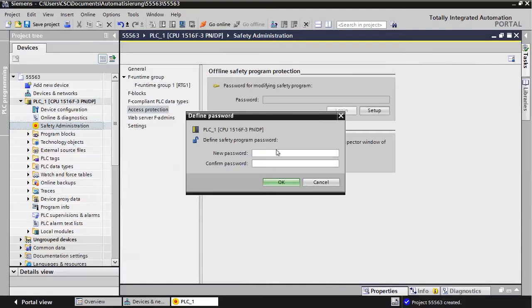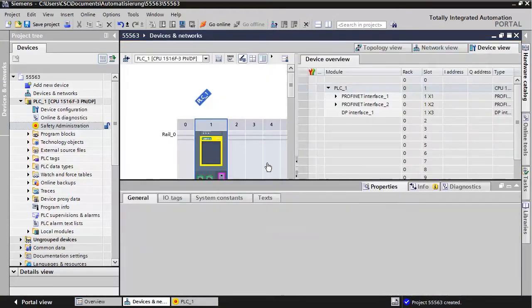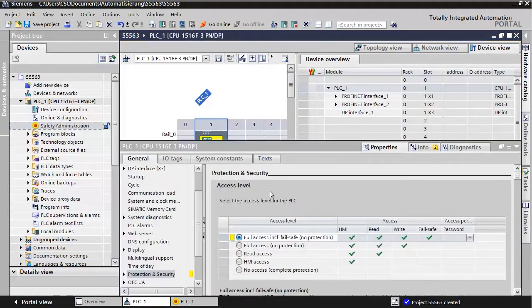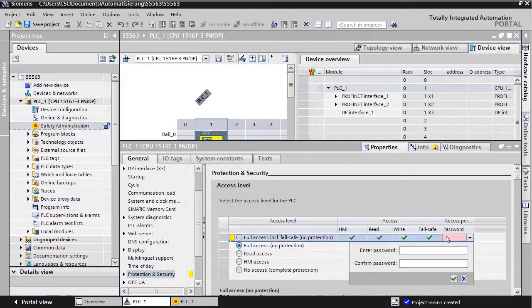Set the password for the offline safety program protection if desired. If you want, you can also set a password for the access level protection on the PLC. Click on Go to the Protection Area of the FCPU. Change the access level for the PLC to Full access (no protection). Set the password for Failsafe Access.